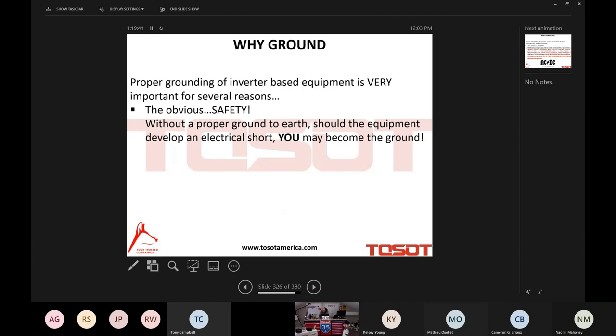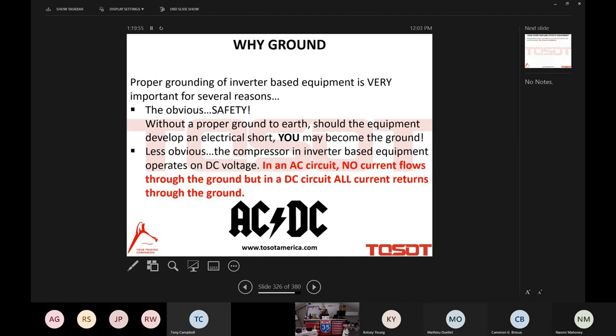It's the reason why the electrical service in this structure is grounded, so that when I do this, I don't become the ground. Because if I become the ground, I'm going to be on the floor, or worse, right? I mean, I get up off the floor. But something we don't consider and need to consider about proper grounding when it comes to all inverter systems, listen to this. Less obvious is that the compressor in the inverter-based equipment operates on a DC voltage.